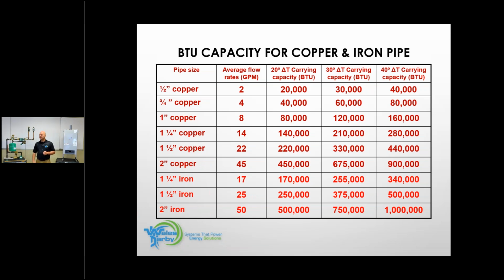So the same gentleman who asked the question basically came back with, so for a condensing boiler, I'm going to use a 30, but cast iron will use a 40. On commercial cast iron, you may see up to a 40, and that's strictly driven around the pipes, but you may also see on that boiler a crossover with a circulator just to protect the iron a little bit better. The system may have the 40 because we want to use smaller diameter piping. Maybe I didn't explain that properly, but that's what we're looking at. We still have to protect the cast iron.